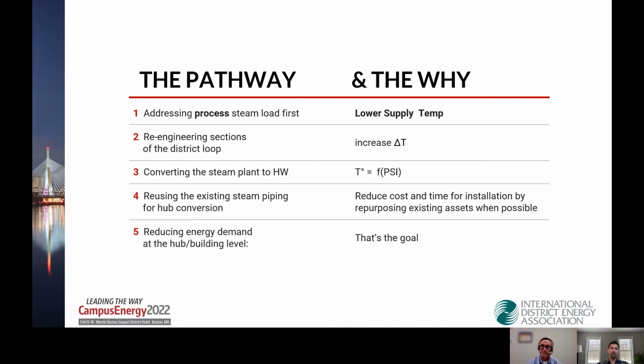Also, the third phase will have to convert the existing steam plant to hot water. We don't want to maintain this complex operation where the temperature is related to the system pressure. So we want to lower the supply and return temperature of the loop, and we have to address this way of producing hot water at the plant.